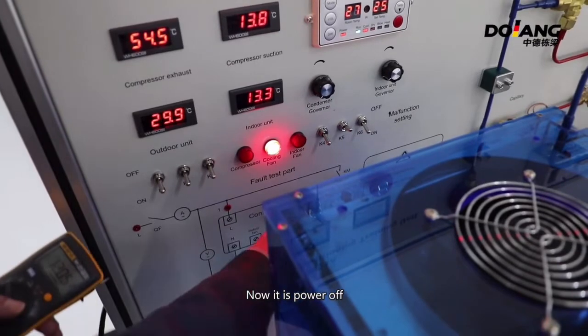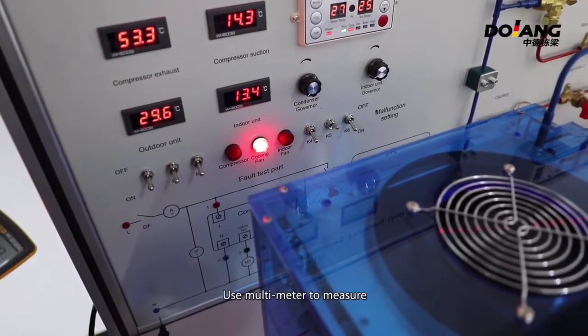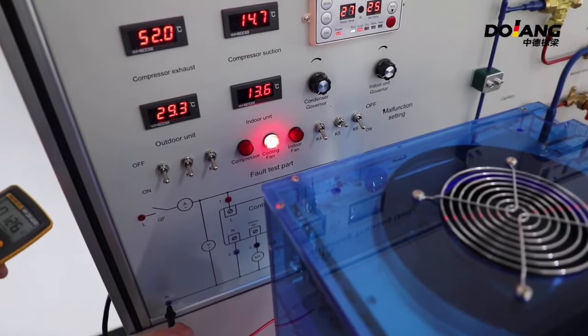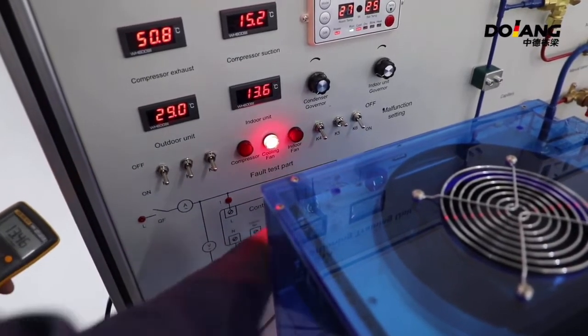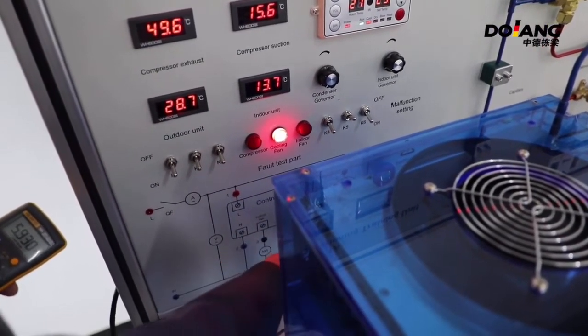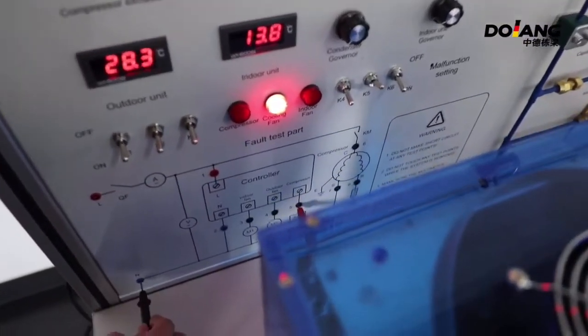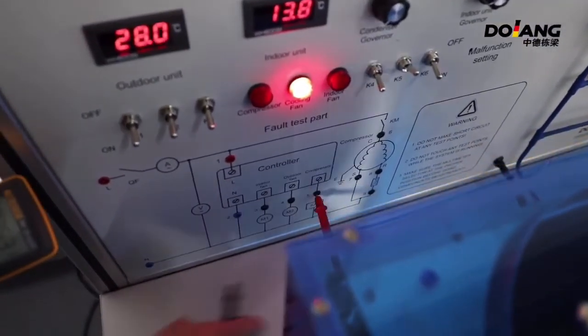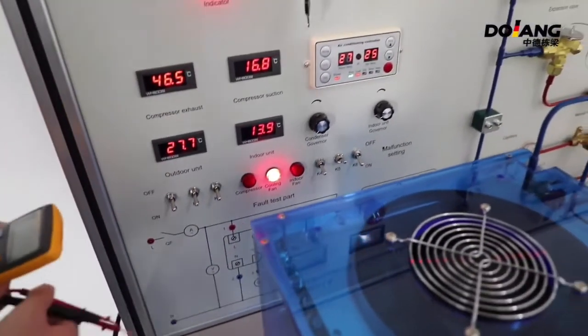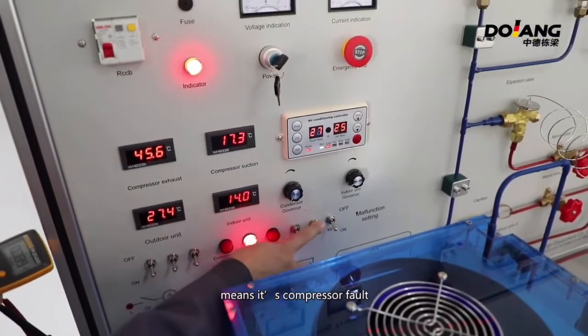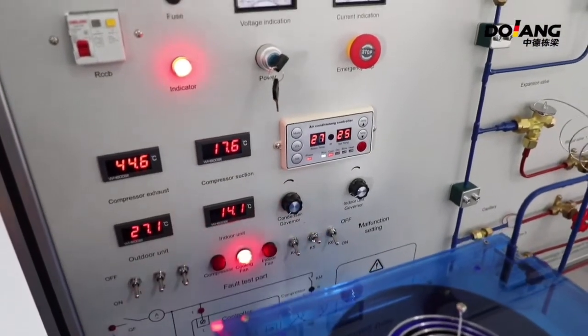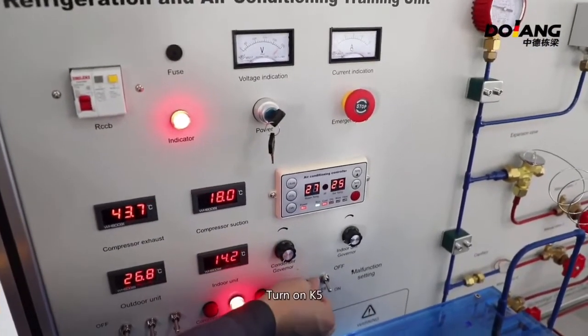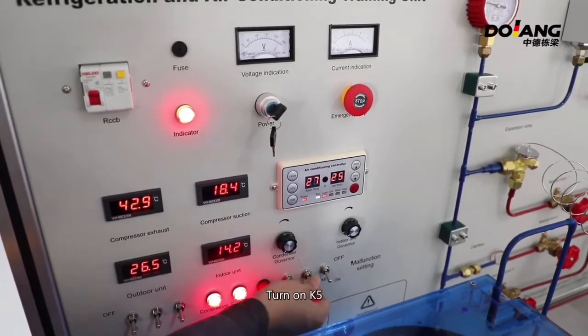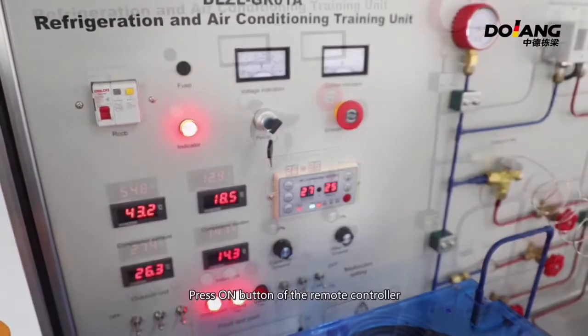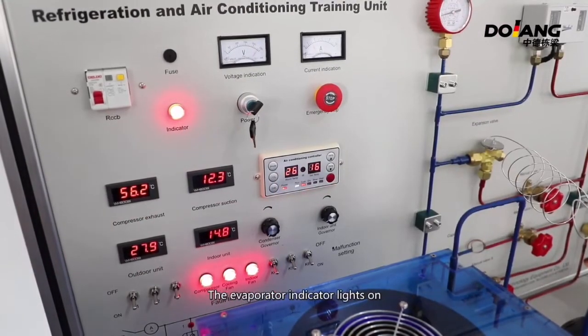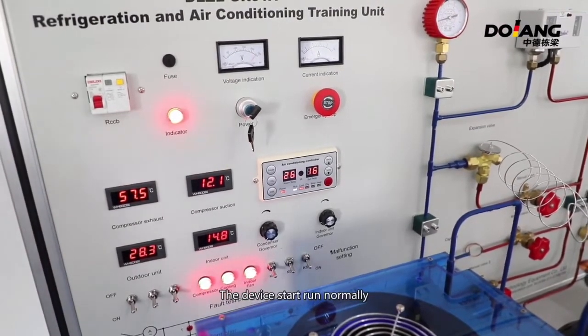Now it's powered off. Use a multimeter to measure it. It means it's a compressor fault. Turn on K5. Press the on button of the remote controller. The evaporator indicator lights on, and the device runs normally.